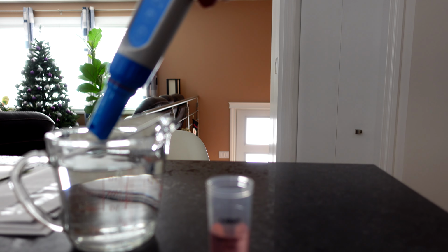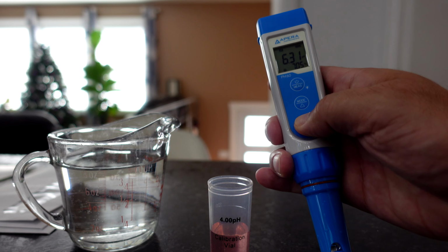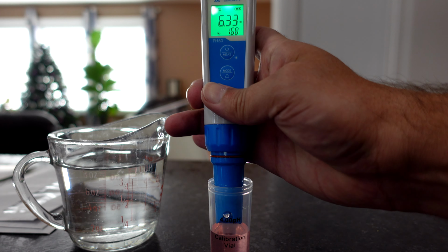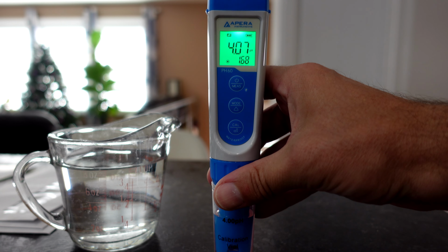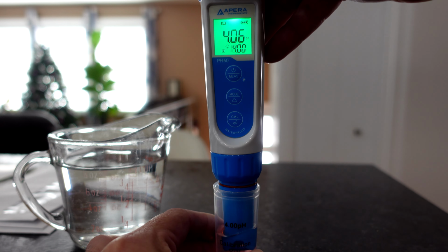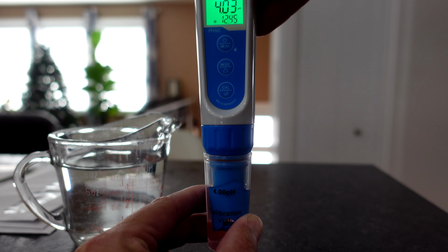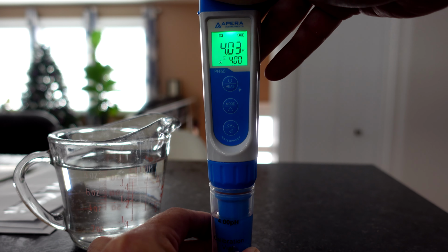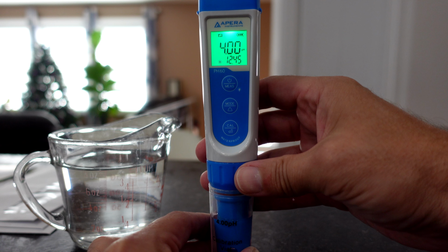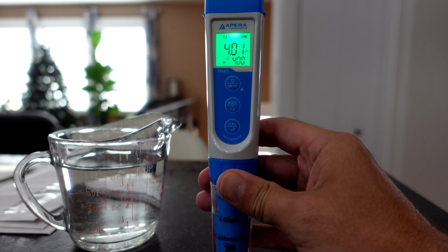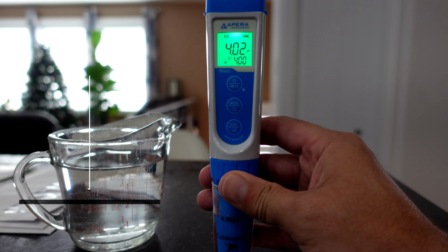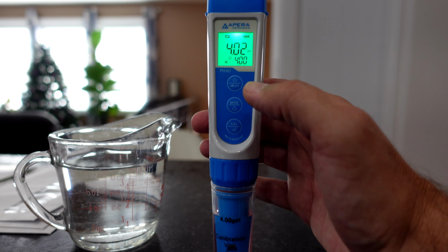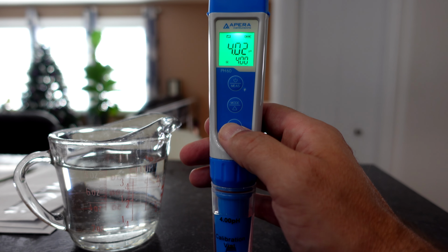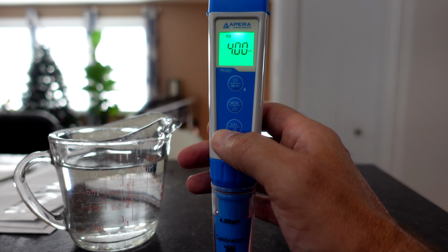All right, with our probe rinsed, it's time for the 4.0 solution. Next, we're going to long press on the calibration. Perfect. And into the 4.0. Same thing here, we're going to give it a little swish. And we're looking for the smiley face there. And a 4.0 on the bottom. Once we do have that, we can push calibrate. And there we go.